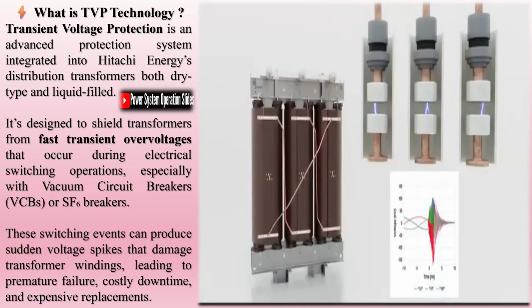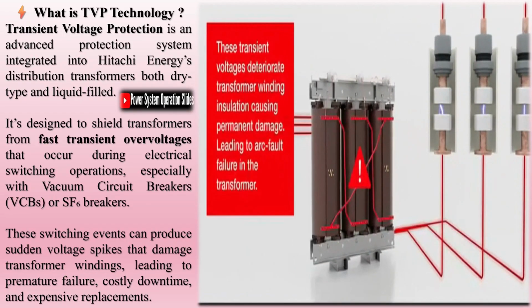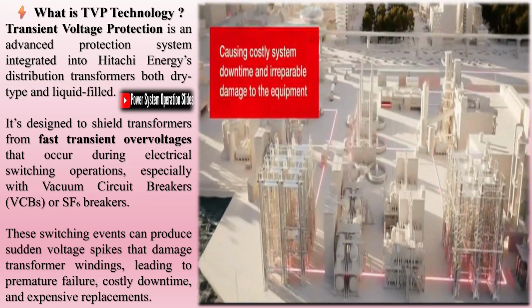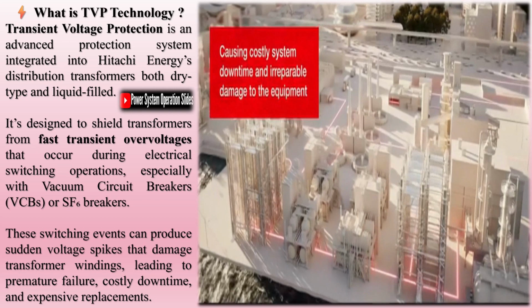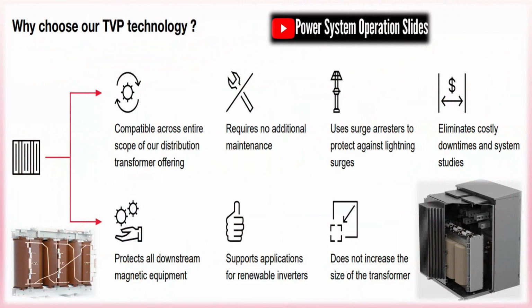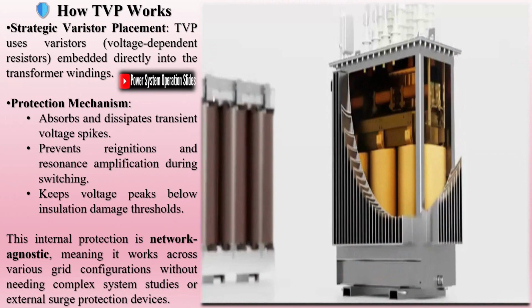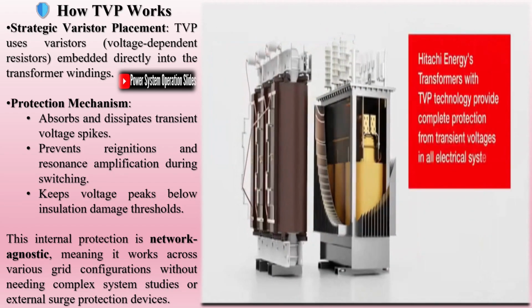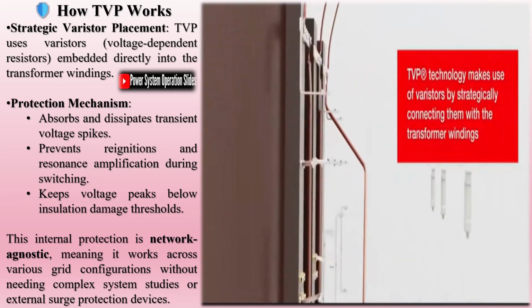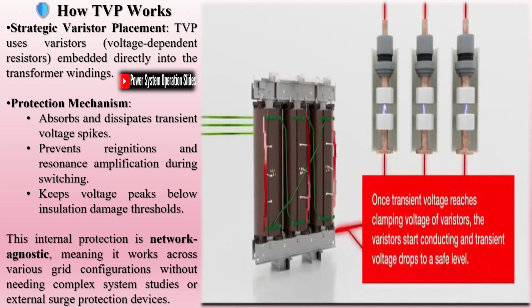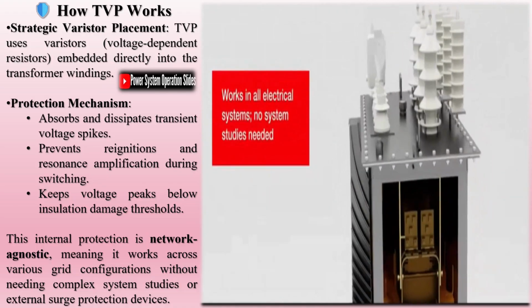However, the sudden drop in current that occurs when the circuit is broken causes a sudden, short-lived overvoltage known as a transient voltage. As more system studies were conducted, newer failure modes caused by such transient voltage were observed. Transient voltage protection is an advanced protection system integrated into Hitachi Energy's distribution transformers, both dry-type and liquid-filled. It's designed to shield transformers from fast transient overvoltages that occur during electrical switching operations, especially with vacuum circuit breakers (VCBs) or SF6 breakers. These switching events can produce sudden voltage spikes that damage transformer windings, leading to premature failure, costly downtime, and expensive replacements.